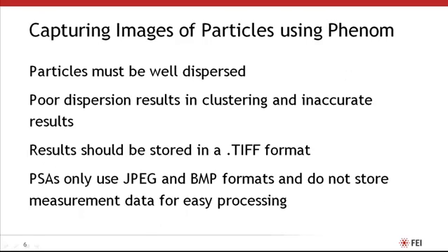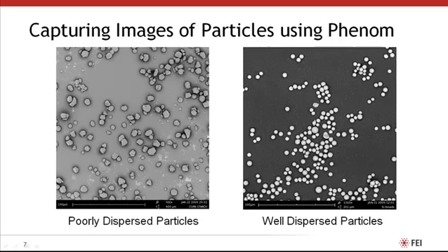Now we're going to go over a few pointers for how to capture images of particles using the Phenom. First of all, the particles must be well dispersed on the sample stub. Poor dispersion can result in clustering and inaccurate results using the particle size software. Results should also always be stored in TIFF format, because JPEG and BMP formats do not store measurement data for easy processing. On the left-hand side, poorly dispersed particles are lying one on top of another, giving poor results, whereas on the right-hand side, well-dispersed particles will give highly accurate results in Scandium software.